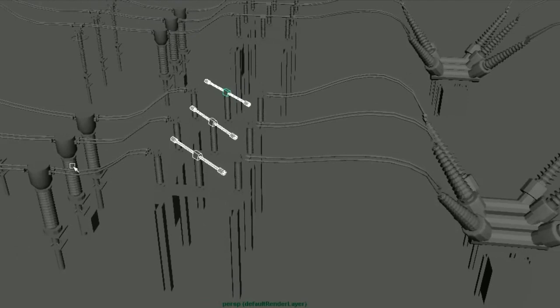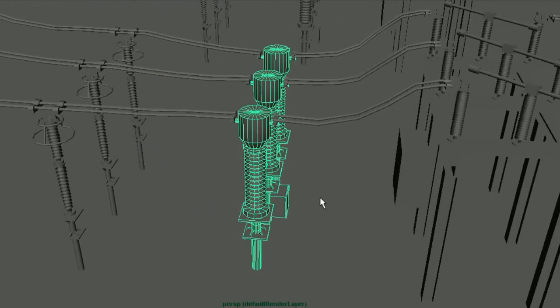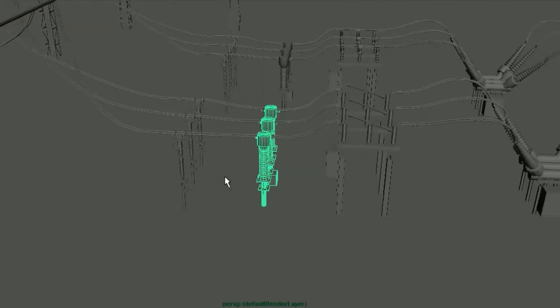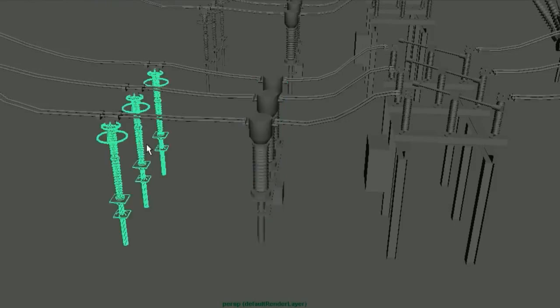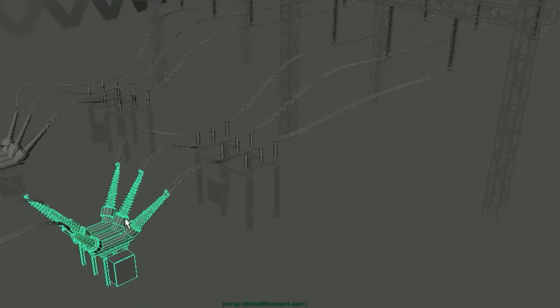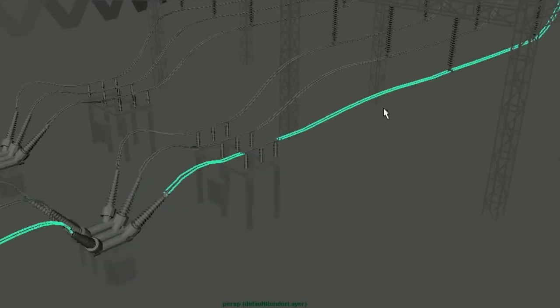To measure how much current is flowing in the transmission line, current transformers are installed in each phase. Whatever current flows through the line passes through the current transformer, which reduces it in the secondary circuit — for example, if 1000 A flows in the line, 10 A will flow in the secondary winding. We can measure this reduced current with a small standard-size ammeter. Surge arresters are also installed near the circuit breaker and current transformer to protect them from voltage surges. After this arrangement, the conductors continue to the transmission line.